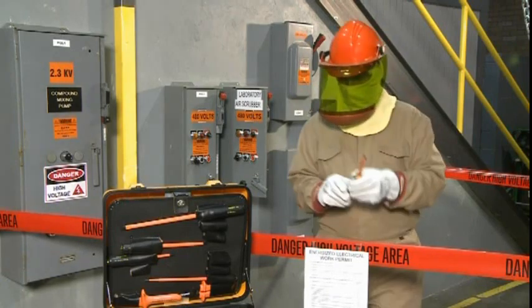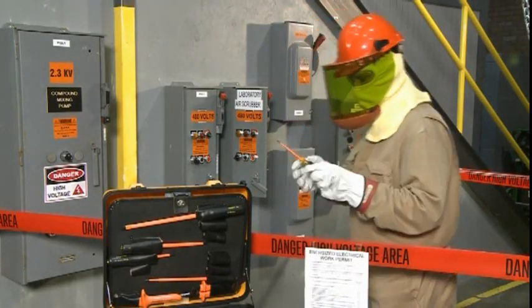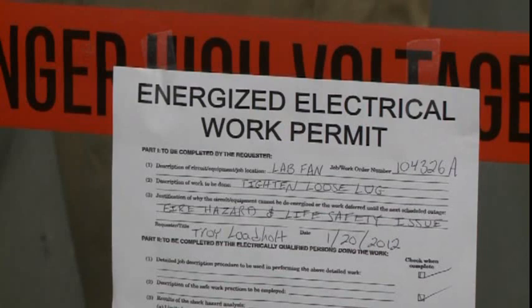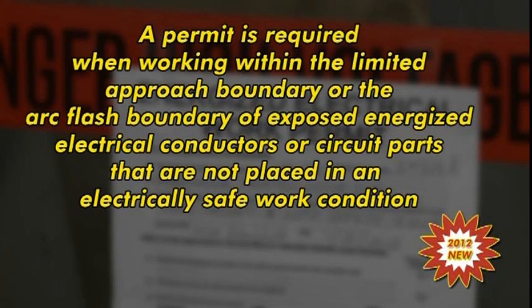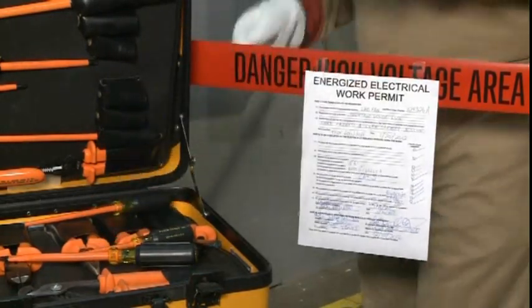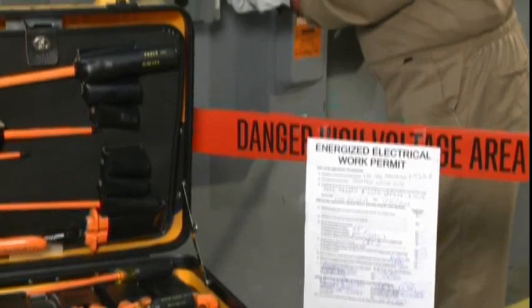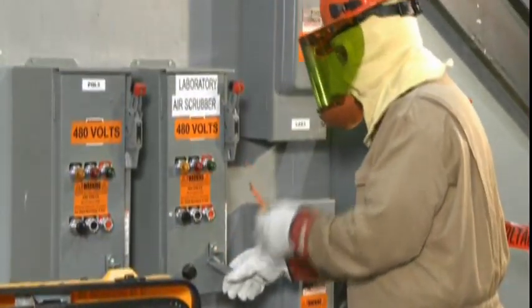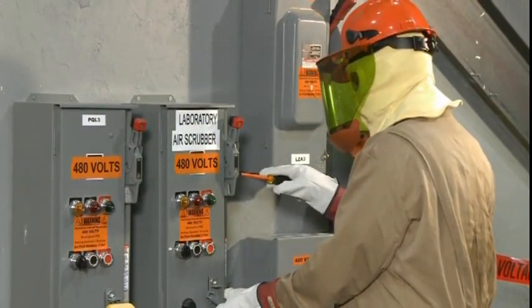When these conditions are met, working on energized conductors or circuit parts is permitted. However, with limited exceptions, this energized repair work shall only be done with an approved, written, energized electrical work permit. A change made to the 2012 NFPA 70E requires an energized electrical work permit when working within the limited approach boundary or the arc flash boundary of exposed energized electrical conductors or circuit parts that are not placed in an electrically safe work condition. The purpose of the energized electrical work permit is to ensure that all hazards are considered and all precautions taken before work is performed on energized parts.